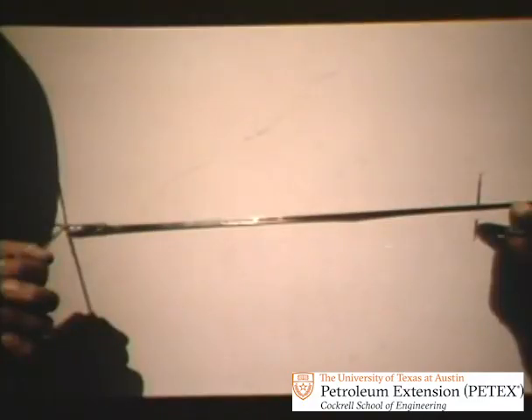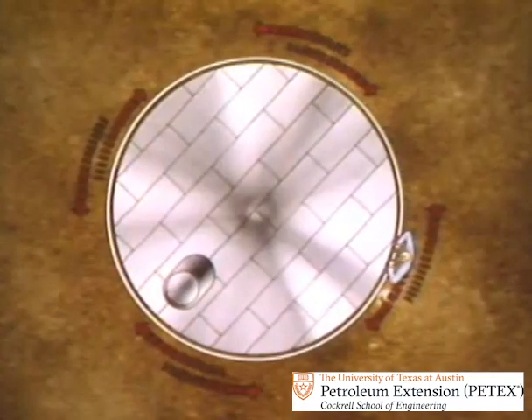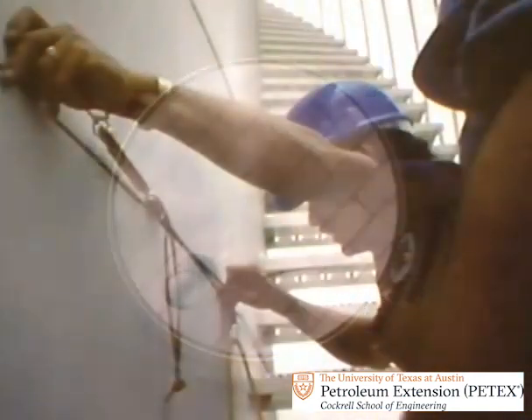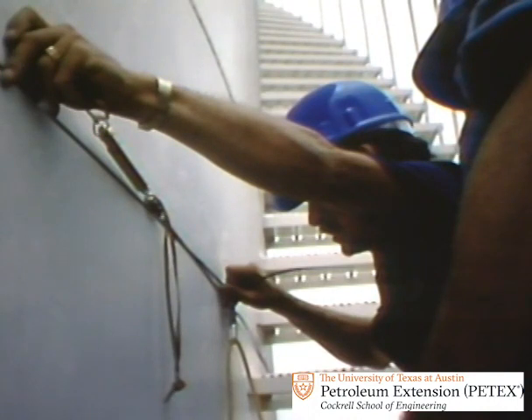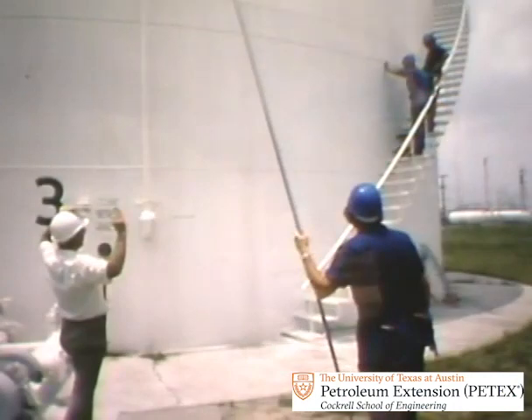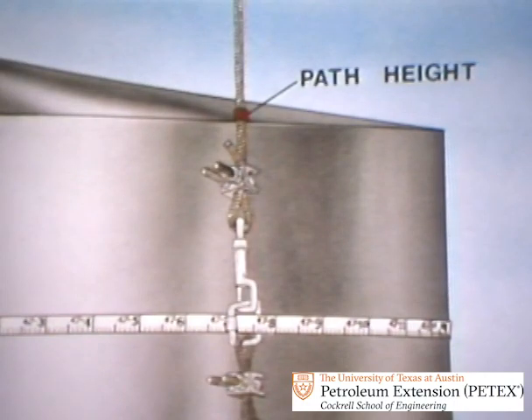To calibrate the working tape, the crew places it on the tape path used for the standard tape. They break surface tension by sliding the tape back and forth and apply enough tension to the tape to get it to read the same as the standard tape. This calibrates the working tape. Once calibrated, the working tape is used to measure the circumference of the remaining rings. This is after the tape paths are carefully marked. Because of its height, the top ring requires a special metal ring and lines to hold the tape and mark the path height on the top ring.